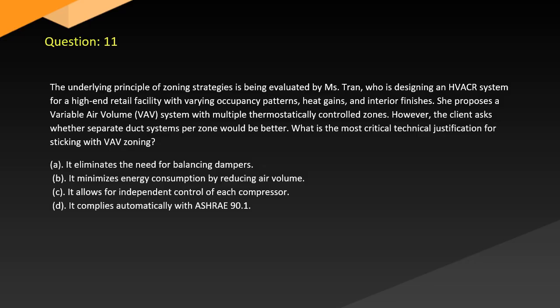Question 11. The underlying principle of zoning strategies is being evaluated by Tran, who is designing an HVACR system for a high-end retail facility with varying occupancy patterns, heat gains, and interior finishes. She proposes a variable air volume system with multiple thermostatically controlled zones. However, the client asks whether separate duct systems per zone would be better. What is the most critical technical justification for sticking with zoning? A. It eliminates the need for balancing dampers. B. It minimizes energy consumption by reducing air volume. C. It allows for independent control of each compressor. D. It complies automatically with ASHRAE 90.1.